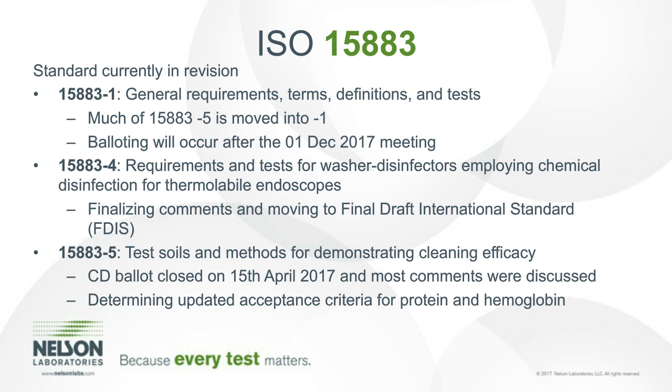standard. As for the -5 that is focused on test soils, that is quite completed, but there is still a lot of debate about determining updated acceptance criteria for protein and hemoglobin as action and alert limits. They are still not sure if the benchmark specified in TR 30 is appropriate for Europe. Are they comfortable with those acceptance criteria?